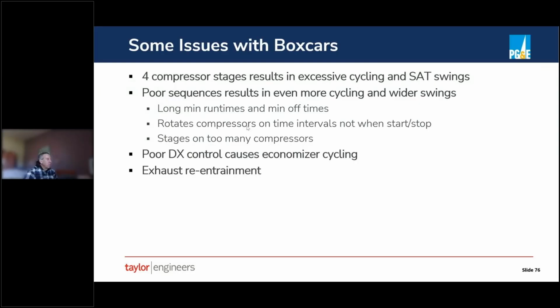It did weird things with rotating compressors, turning on too many compressors. And so what was happening is that DX was fighting both the economizer and the evaporative cooling. In the end, it became very difficult to control the units, and they had to make it somewhat of a non-integrated system between the three. There were also significant issues with exhaust reentrainment. Those packaged box cars only come in one flavor in terms of where the outside air comes in and where the exhaust goes out, and it was very hard to arrange them so that one wasn't blowing hot air into another. So there are some practical issues there.